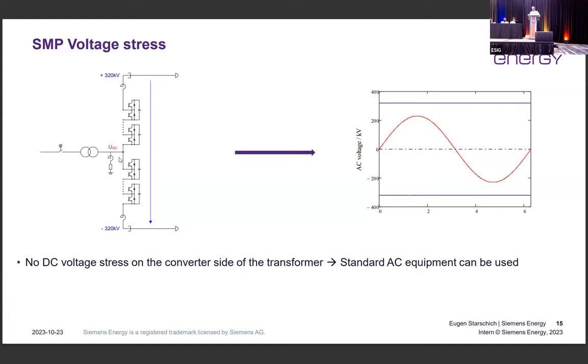There are two advantages. The maximum voltage acting as a DC voltage is actually 640 kV, but you break it up into plus 320 and minus 320. That means all the equipment you design, like the bushings, reactors, DC cables, DC cable sealing ends, and so on, is designed for 320 kV. And we don't have a DC voltage stress on the converter side of the transformer. This is a key feature of the symmetrical monopole.